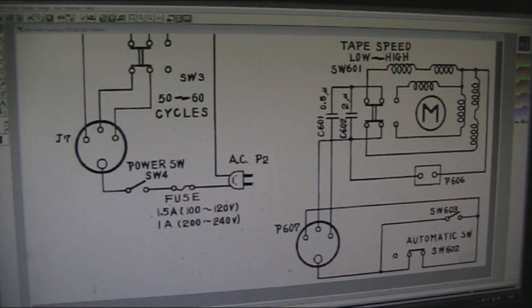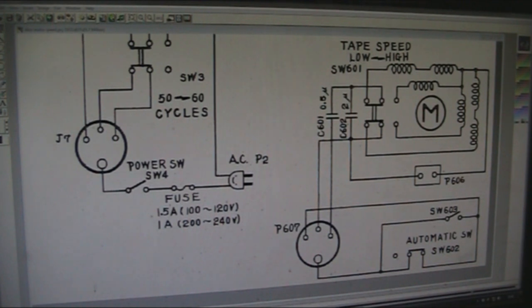That's the way it was set up, and when he was looking on the inside of it, he saw this capacitor in there, and just above it, it said to change the capacitor depending on what frequency you're using. So essentially, he needed to change the capacitor for one microfarad, if I remember right, to run it on 50Hz.